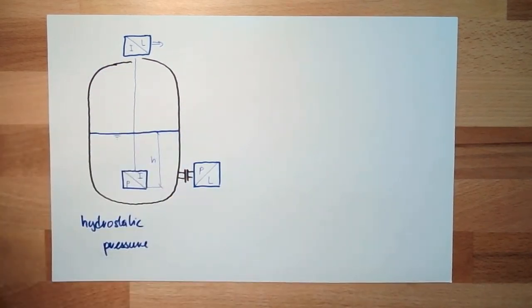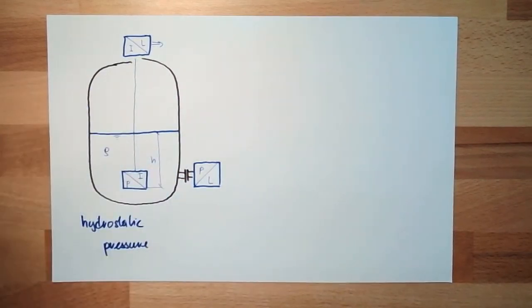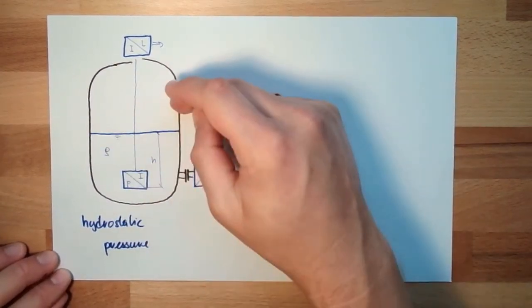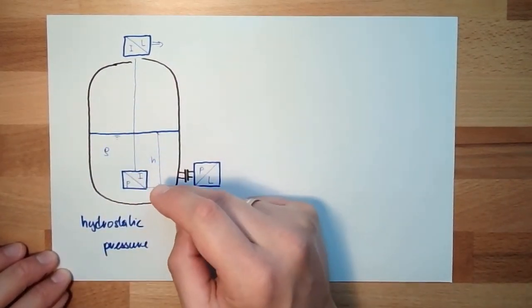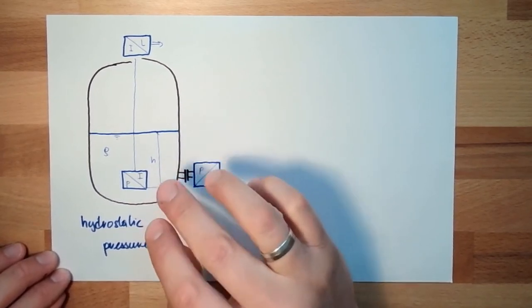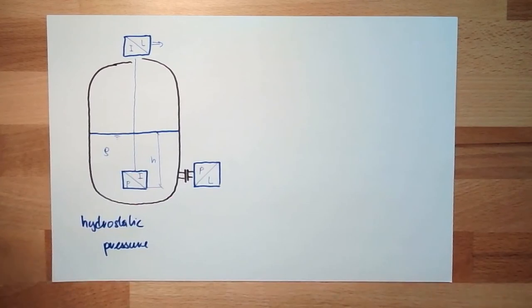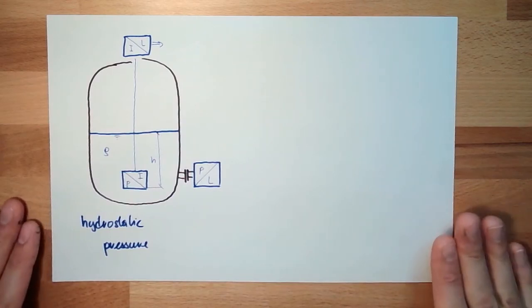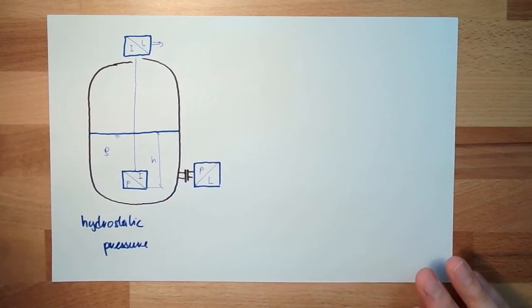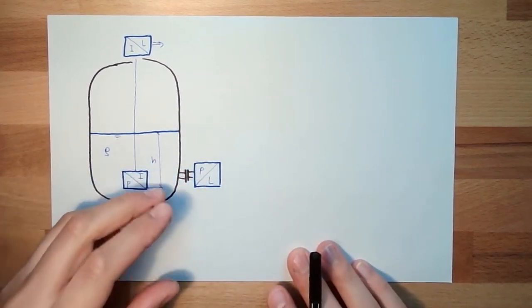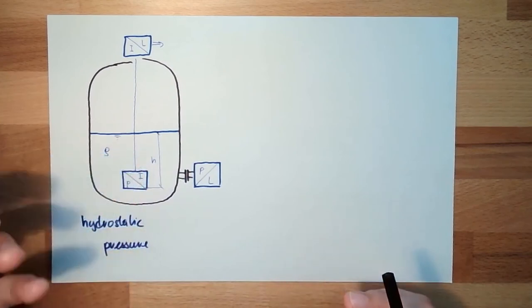However, I'm also depending on the specific weight, the density of this material. Also, if this is a pressurized tank — there is a P₀ inside — this is not working very well, because I have to measure the pressure of the air and the pressure of the liquid, so I have to measure differential pressure. Of course it's working, but then it's getting expensive. Also a problem if this liquid is very aggressive — you might not find a suitable membrane for the pressure measurement.